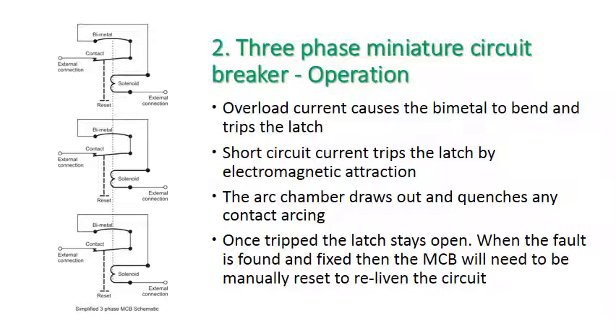So if you have an overload current in one or more bimetal strips, the bimetal heats and starts to bend, and eventually, if the overload is maintained, the mechanism will be tripped and the circuit breaker will stop the current flow. At this point, there's not enough magnetism in the electromagnetic trip mechanism, or the solenoid in this picture, to cause the trip to happen. But if the fault is more severe and short circuit current flows, then definitely you're getting enough magnetism for the solenoid to pull the mechanism open, and the circuit breaker will trip very quickly.